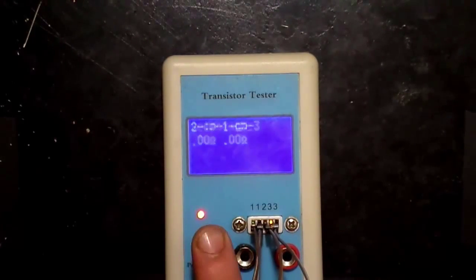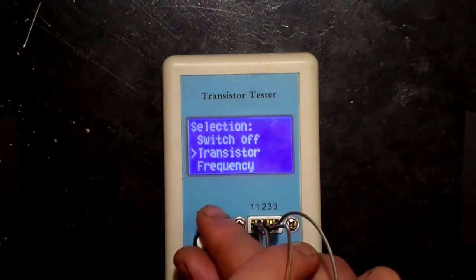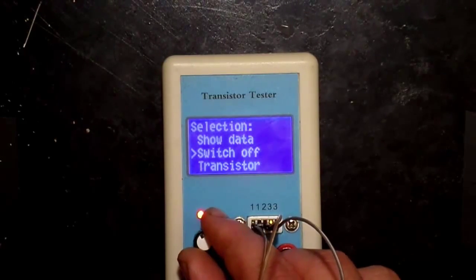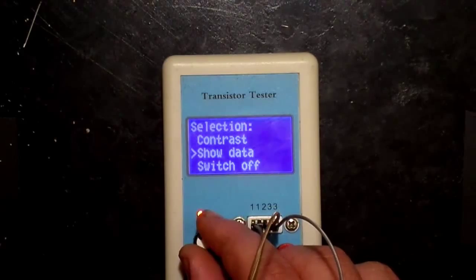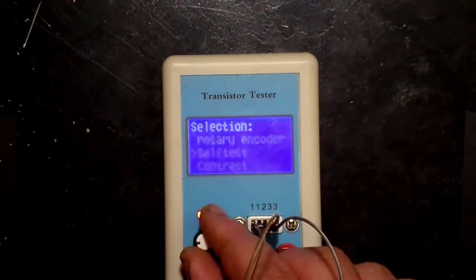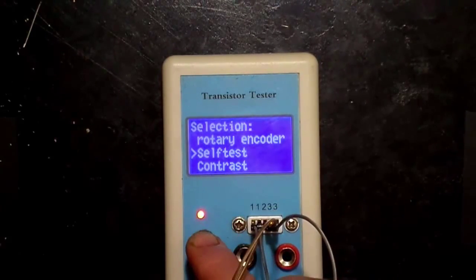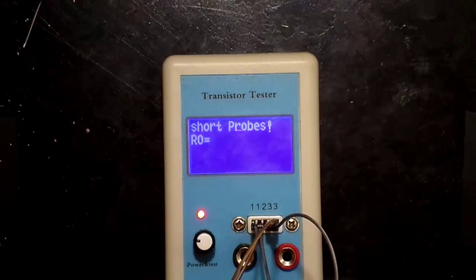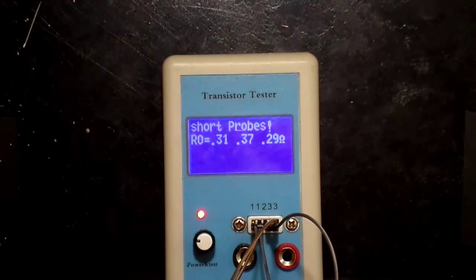Now push and hold for 2 seconds until the menu display. Rotate the knob until you have selected the self test, and then push down on the rotary encoder. The self test has now started.